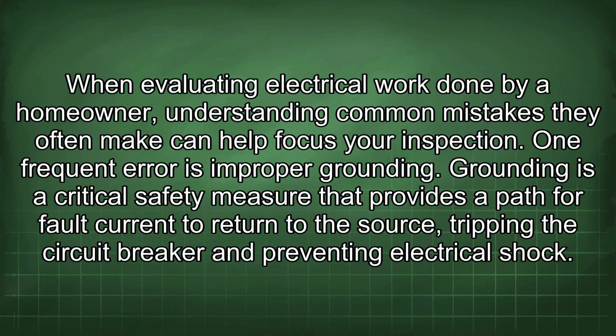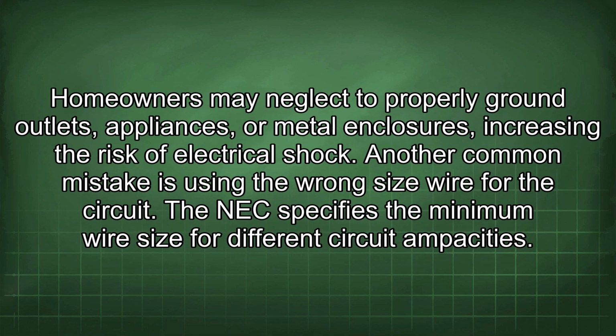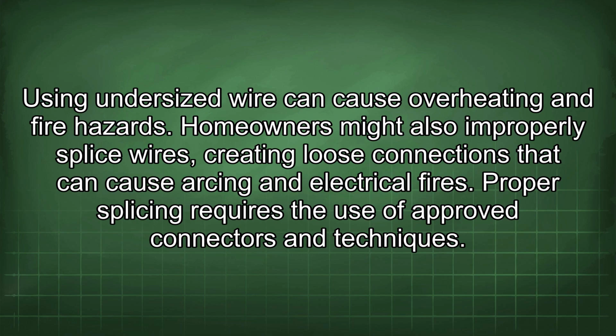Grounding is a critical safety measure that provides a path for fault current to return to the source, tripping the circuit breaker and preventing electrical shock. Homeowners may neglect to properly ground outlets, appliances, or metal enclosures, increasing the risk of electrical shock. Another common mistake is using the wrong size wire for the circuit. The NEC specifies the minimum wire size for different circuit ampacities. Using undersized wire can cause overheating and fire hazards.